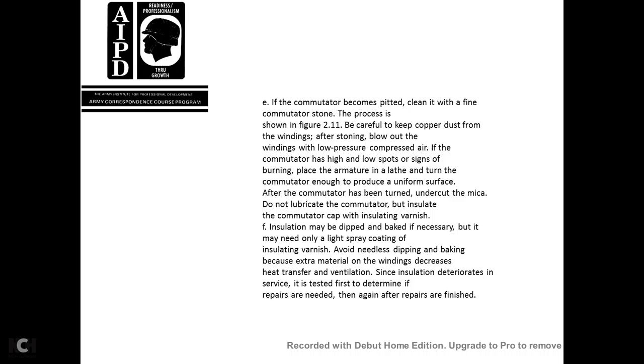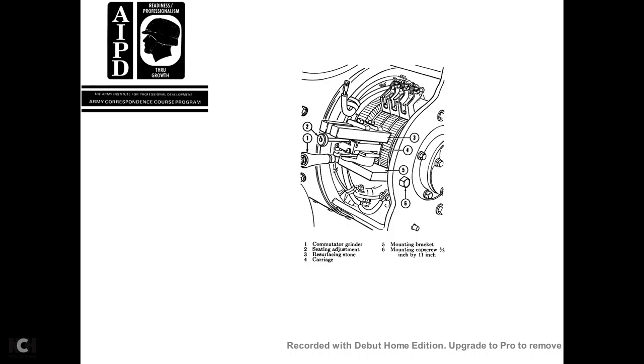After the commutator has been turned and the mica undercut, do not lubricate the commutator. Insulated windings may be dipped and baked if necessary, but a light spray coating of insulating varnish may be all that is needed. Avoid needless dipping and baking, because excess material on the windings decreases the heat transfer to ventilation. Since insulation deteriorates, surfaces are tested first to determine if repairs are needed, then again after the repairs are finished. This shows the commutator grinding, seating, and adjustment, resurfacing stone carriage, the mounting bracket, and the mounting cap screws.